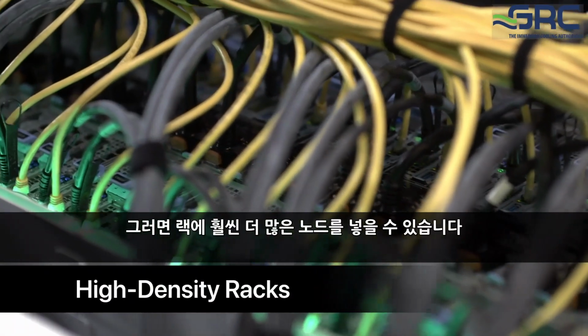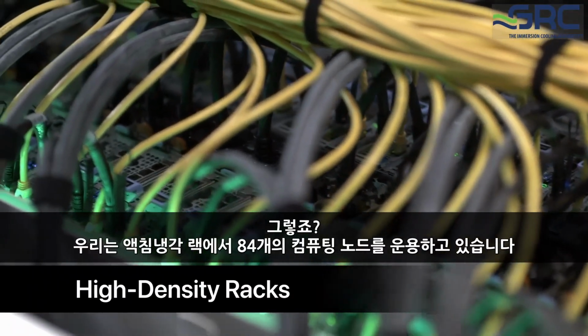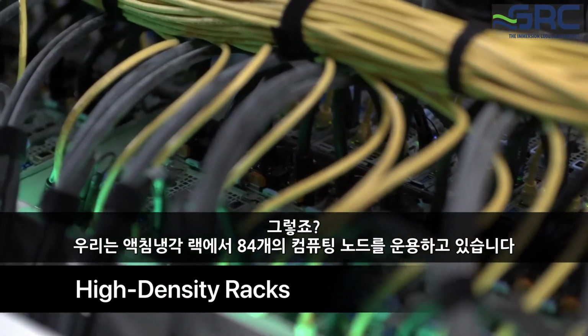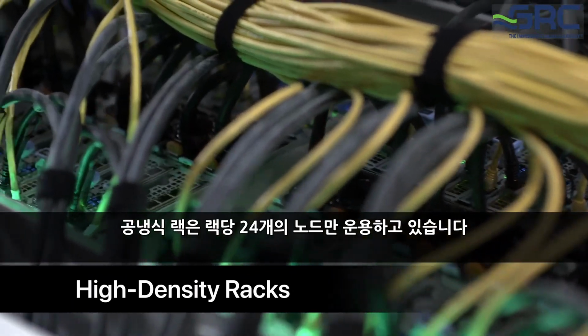And then we can put a lot more nodes in a rack. We're running at 84 compute nodes in a rack in the immersion-cooled racks. The air-cooled side, we're only running at 24 nodes per rack because we just don't have the airflow or any other cooling solution to get to that density.